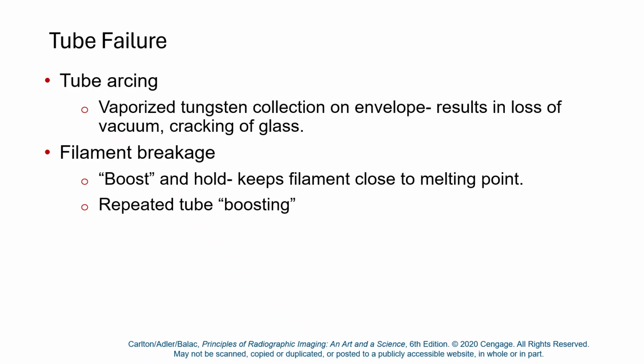Now, again, in pediatric chest X-rays, you are going to have to prep and wait for the child to take in a big breath of air before you expose. So you are going to run preparation or boost a little bit longer and hold that before exposure. Just know over time you are reducing the life of the X-ray tube.